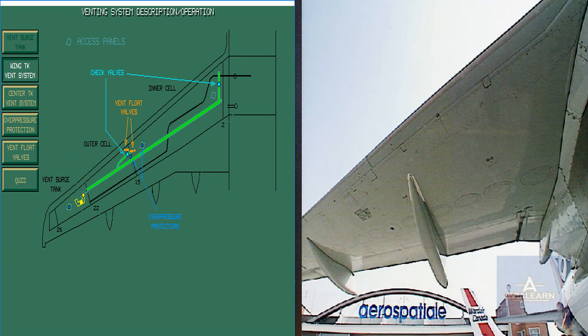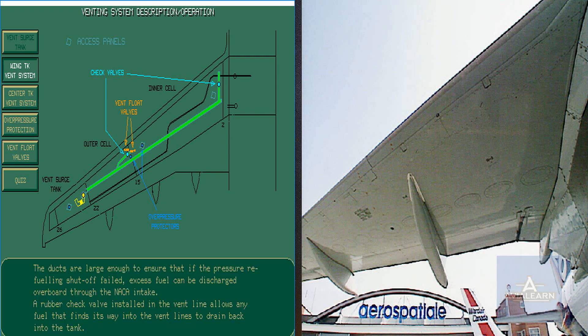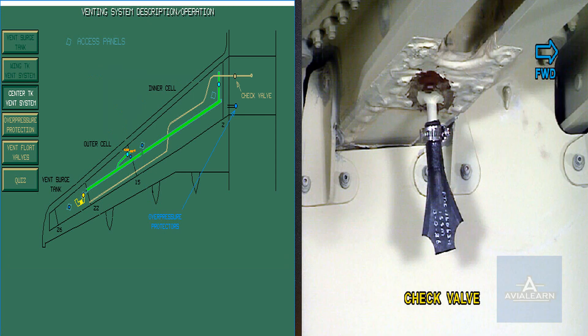Each wing tank inner and outer cells vent to the related vent surge tank. The vent lines are fitted with a vent float valve. The center tank vents into the left-hand vent surge tank.